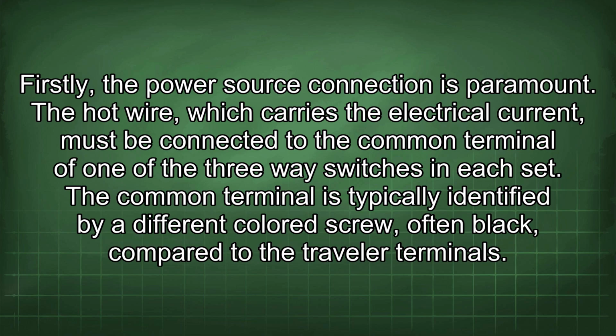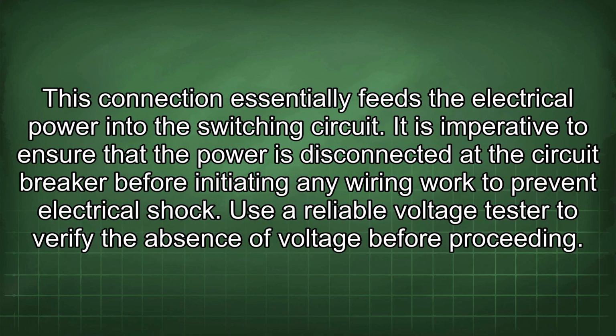Firstly, the power source connection is paramount. The hot wire, which carries the electrical current, must be connected to the common terminal of one of the three-way switches in each set. The common terminal is typically identified by a different colored screw, often black, compared to the traveler terminals. This connection essentially feeds the electrical power into the switching circuit. It is imperative to ensure that the power is disconnected at the circuit breaker before initiating any wiring work to prevent electrical shock. Use a reliable voltage tester to verify the absence of voltage before proceeding.